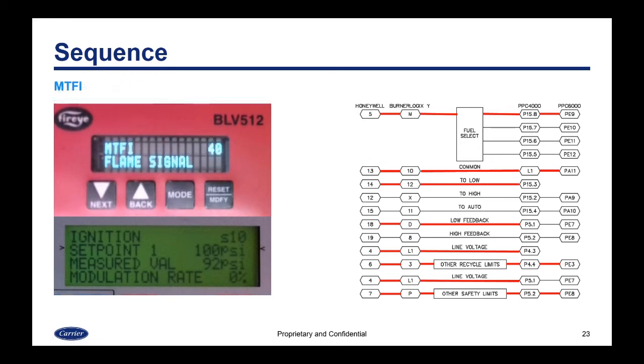Nothing changes between PTFI and MTFI, from pilot to main trial for ignition. The signals are the same. It's still being commanded to the low position. It's still receiving low feedback. The flame safeguard is just going through its sequencing. The PPC, meanwhile, is still going to be at the ignition position.